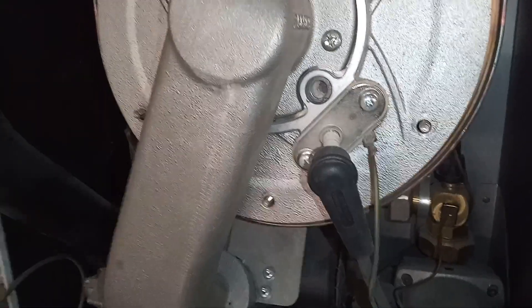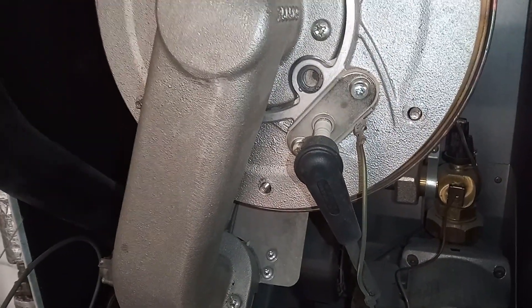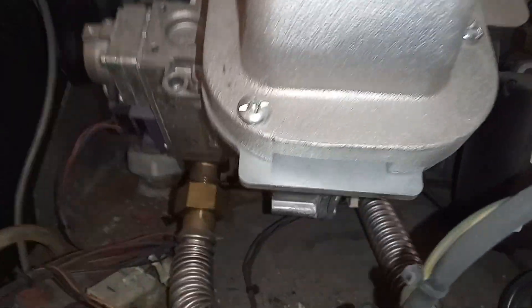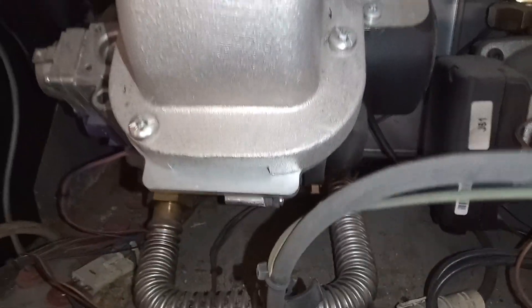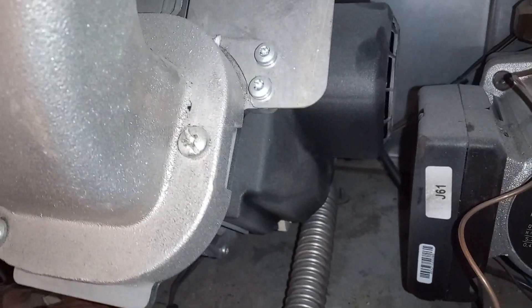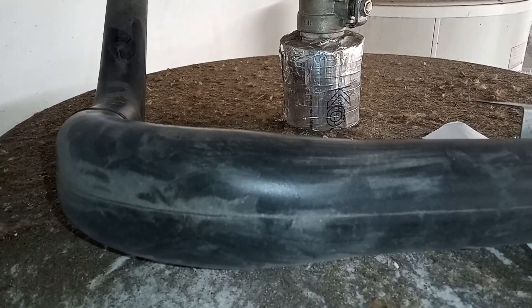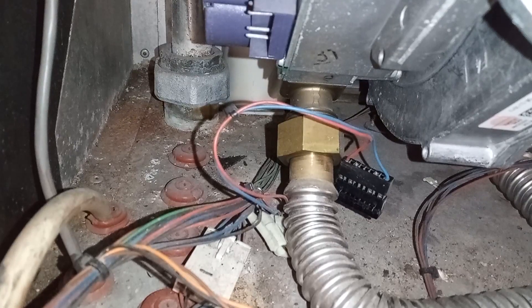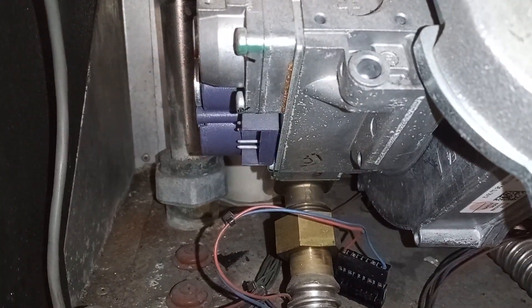Now it's time to take off the spark electrode and the earth. Then we're going to remove the connection to the gas valve, power to the fan, and the modulating connection to the fan. We've got our venturi out of the way and the air inlet disconnected from the venturi. Now just disconnecting the gas connection to the gas valve.